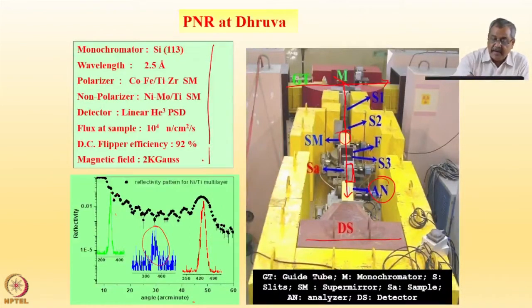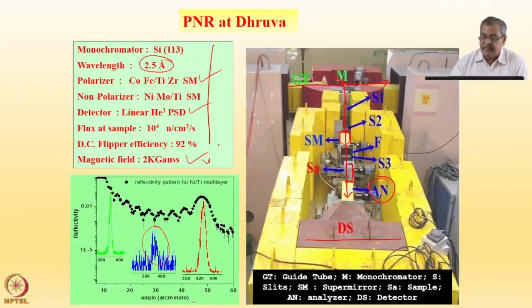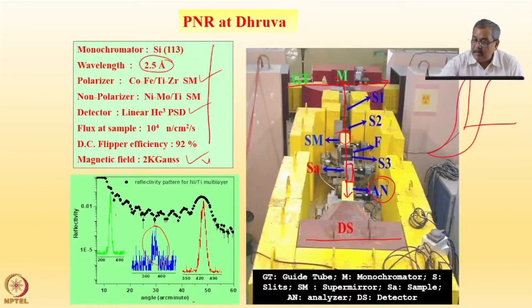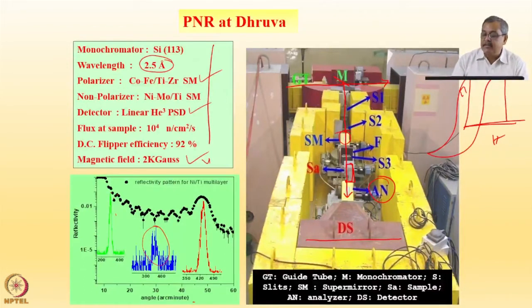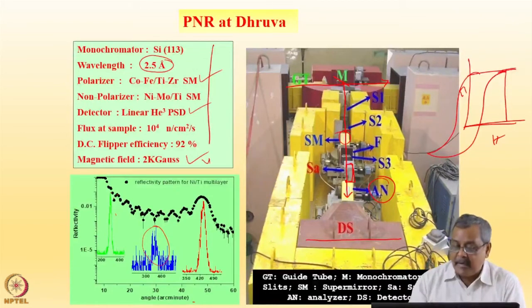At the moment these specifications are slightly changed. The wavelength we have gone up to 3 angstrom. It's a cobalt-iron-titanium-zirconium supermirror. We also have a non-polarizer supermirror. The detector is a linear helium-3 detector. We have a DC flipper neutron beam flipper with an efficiency of 92 percent, and we have a 2 kilogauss permanent field on the sample to magnetize it. Usually thin films have low saturation magnetization in their hysteresis loops. We should saturate the thin film so that the magnetization is aligned in one direction.